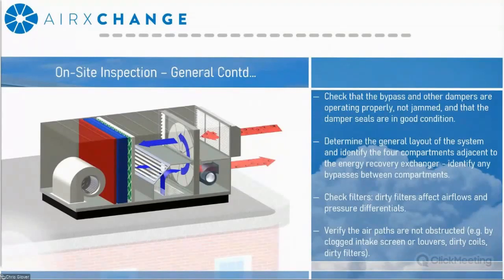Check for gross leakages. Check to see if the filters are dirty. Dirty filters are going to have a significant impact on operating pressure and subsequently airflow. Lastly, you're also going to want to identify any potential obstructions to airflow. So typically you're looking at filters, coils. In my experience, mist eliminators and bird screens get plugged up pretty badly over time, and these are the components that you're going to want to clean and make sure that they're nice and open to maximize airflow delivery.